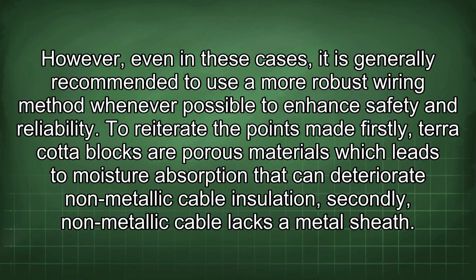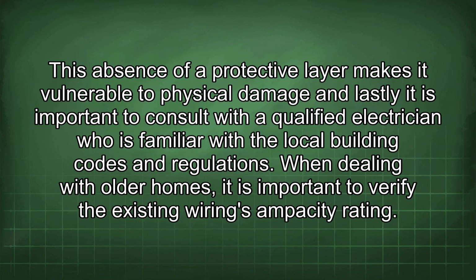To reiterate the points made, firstly, terracotta blocks are porous materials, which leads to moisture absorption that can deteriorate non-metallic cable insulation. Secondly, non-metallic cable lacks a metal sheath. This absence of a protective layer makes it vulnerable to physical damage. And lastly, it is important to consult with a qualified electrician who is familiar with the local building codes and regulations. When dealing with older homes, it is important to verify the existing wiring's ampacity rating.